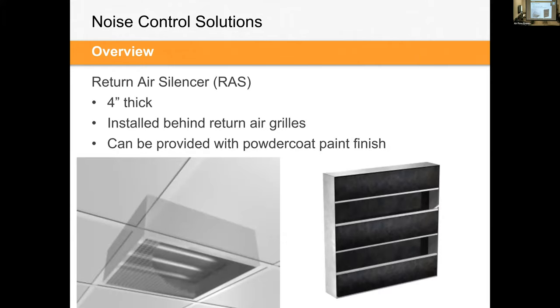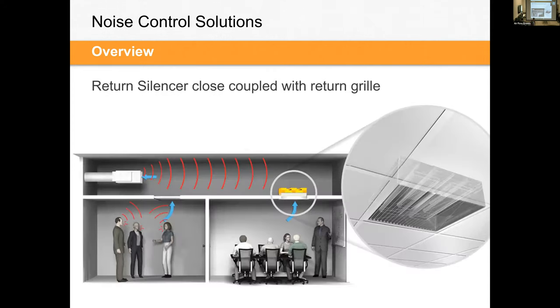An RAS or return air silencer is another very common type. And these are typically 4 inches deep or thick installed behind a return grill. Again, the wall example is a good one where you have a sound source that would be annoying people within an occupied space and you'd want to absorb that sound energy. Or installed in a ceiling like that, where the baffles of that silencer help absorb that sound energy that would otherwise be present.